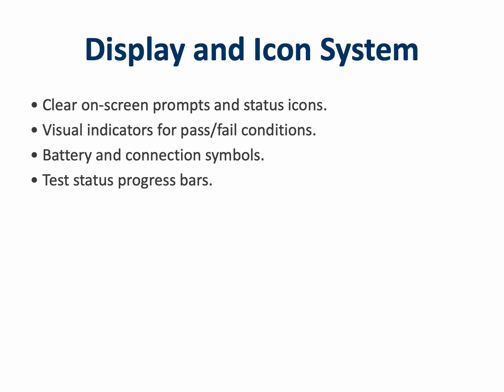The display of the Rigel 288 Plus is more than just a screen. It's an active interface that guides and informs. Icons appear alongside test parameters, reducing the need for excessive text. Pass and fail results are highlighted visually, often with color-coded indicators or bold on-screen notifications. During testing, progress bars show exactly what stage the device is in, helping you monitor timing and sequence flow. Battery life, connection status, and Bluetooth activity are shown continuously at the top of the display, ensuring transparency throughout operation. This combination of visual cues and minimal text keeps testing fast and prevents information overload.